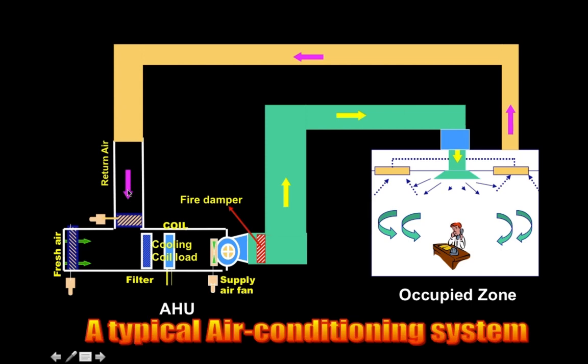That's because this air, the return air, is still pretty cool, and we wouldn't want to throw away all that cool energy out into the atmosphere, into the outside environment. And not to forget that the outside air that we need for ventilation, the 10–15% requirement, has to come from a very hot and humid condition. So there is a high energy penalty if we take high outside air percentages. So a 90% recirculation rate, or roughly 10–15% ventilation requirement, is the common design.